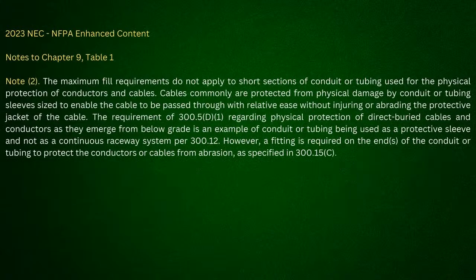Now, if I go look at the enhanced content from NFPA, what does it say? It says the maximum fill requirements do not apply to short sections of conduit or tubing used for physical protection of conductors and cables. Oh, well, so now they're calling it short sections. Okay. Well, normally, what is a short section considered? It's considered a sleeve. Because less than 10 foot. But these are the things I'm trying to point out. Even NFPA is stating here that it's a short section.